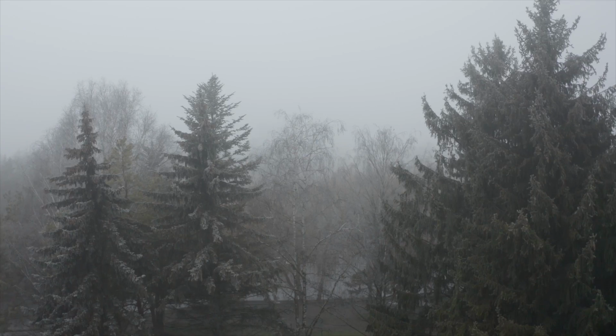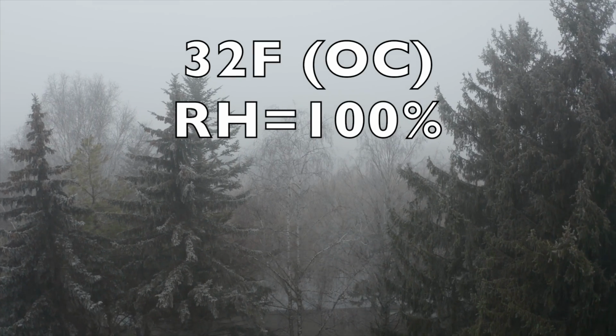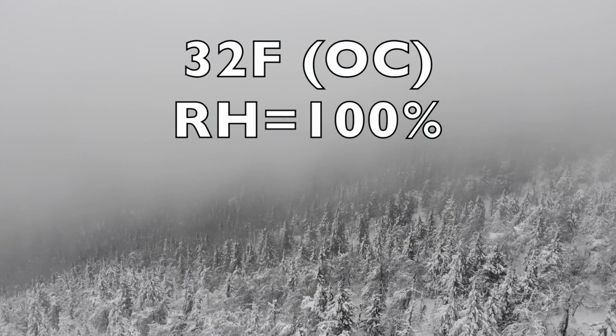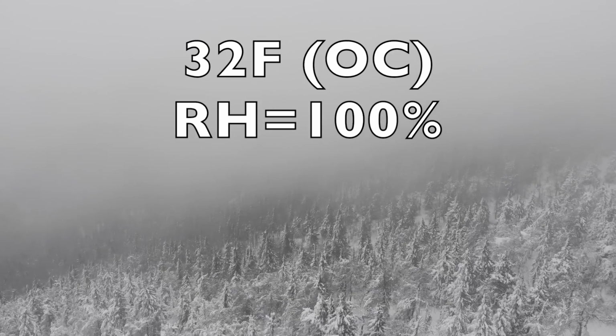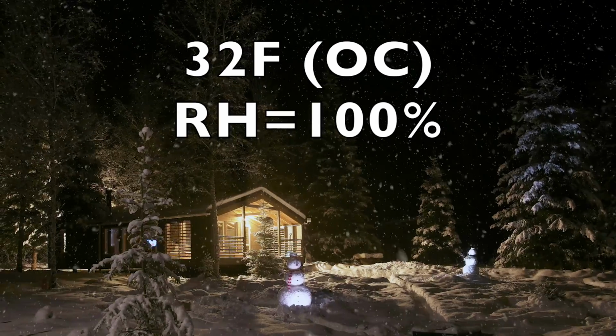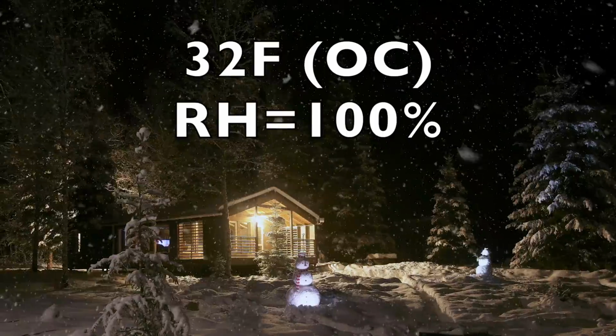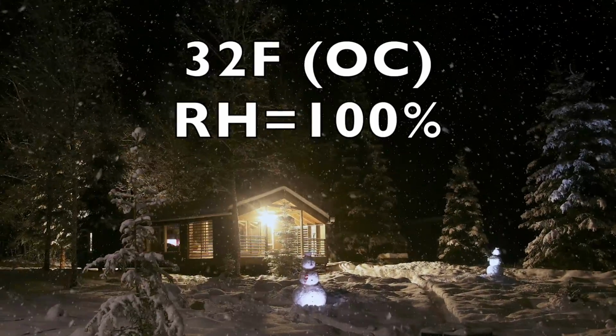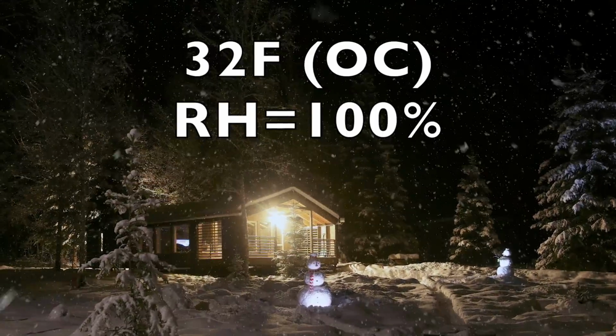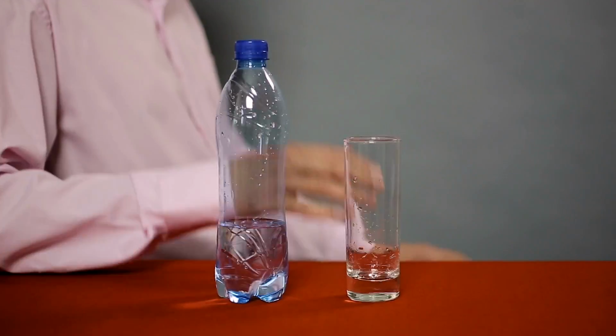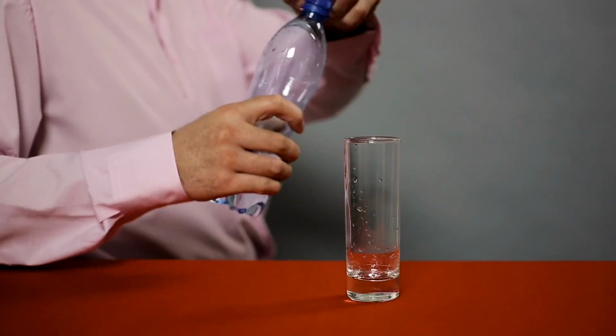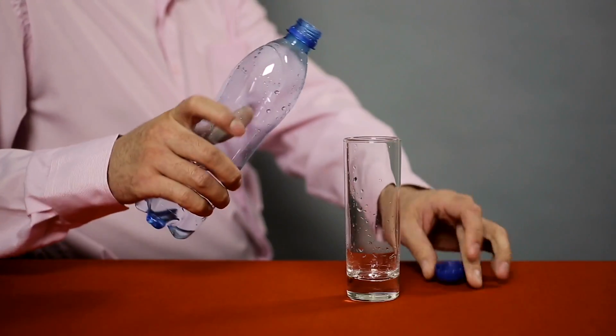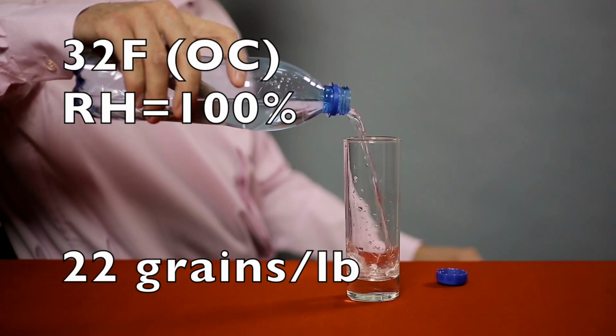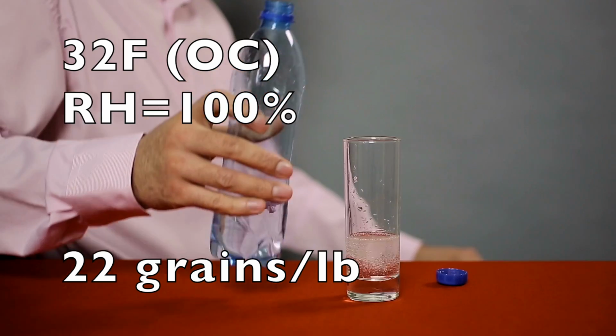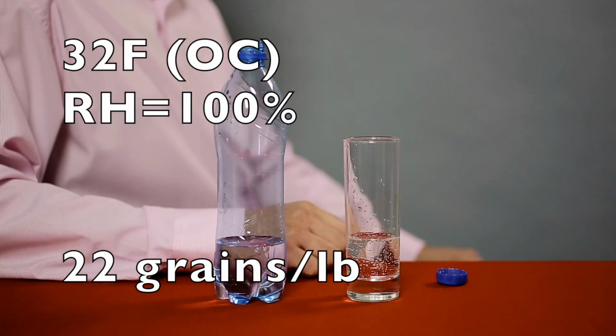Let's say the outdoor air is 32 degrees Fahrenheit and its RH is 100%. Sounds pretty humid, right? What happens when that air leaks into your home? Most people would think, well, since the RH of the outdoor air is 100%, you'd be bringing a lot of moisture into your house. And they'd actually be wrong. This is because when 32-degree air has an RH of 100%, it contains 22 grains per pound of water vapor, which is a relatively small amount of water vapor.